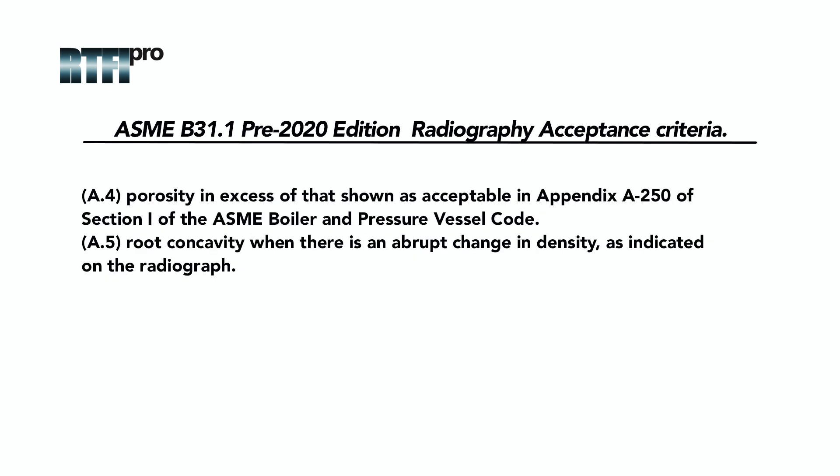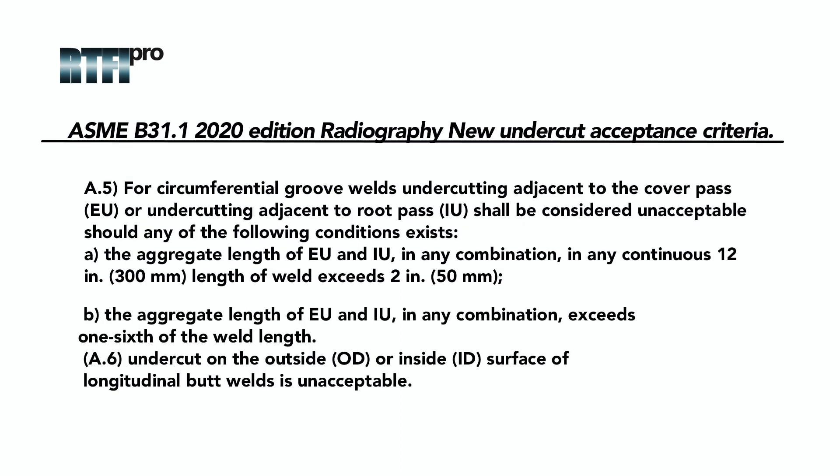A.4: Porosity in excess of that shown as acceptable in Appendix A-250 of Section 1 of the ASME Boiler and Pressure Vessel Code. A.5: Root concavity when there is an abrupt change in density as indicated on the radiograph. With this information, RTFI Pro further went to ASME and requested a code change, which was approved due to discrepancies with undercut not having any acceptance criteria for evaluation.